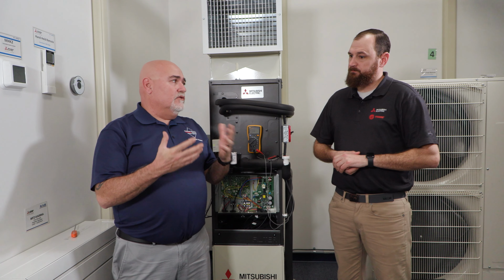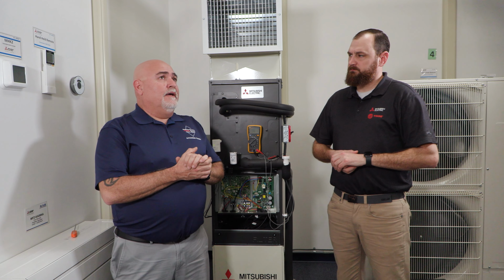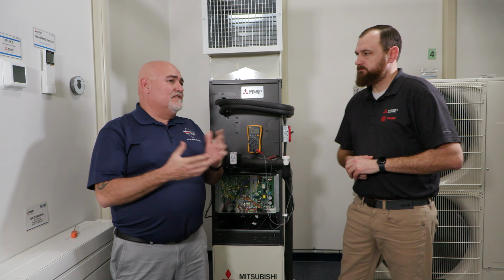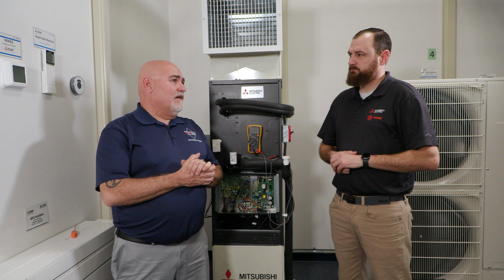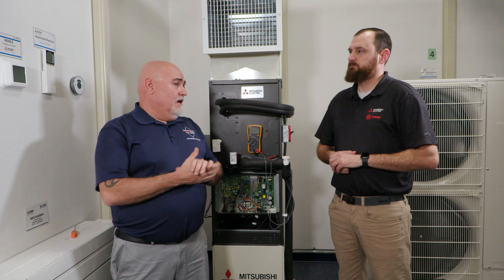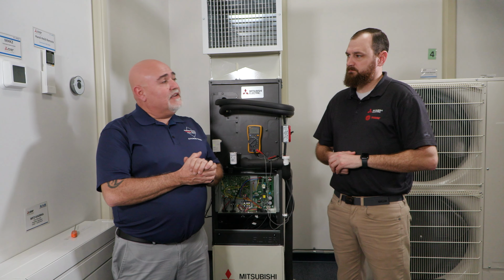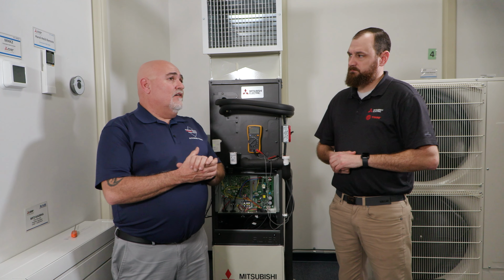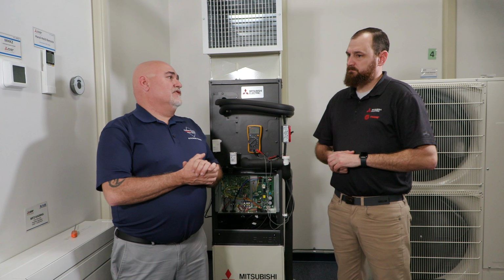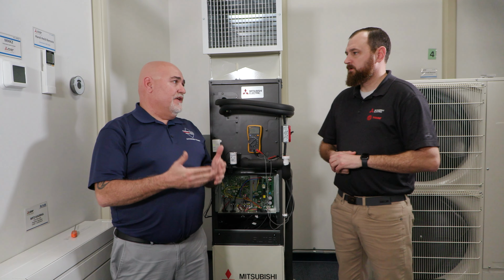So let's talk, Scott, a little bit about the difference between P-Series indoor units and M-Series indoor units. Okay. So P-Series indoor units, the fan rotation acts a little bit differently, right? Diagnosing a P-Series is much different than an M-Series as far as the procedure. If you're diagnosing an indoor fan motor rotational feedback on an M-Series, you're going to want to look that up in the service manual and follow the troubleshooting flow chart.